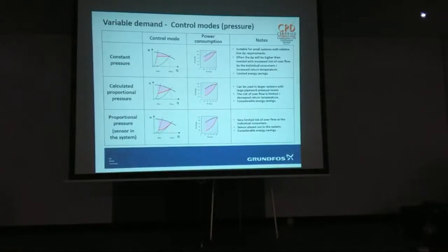Unless you just need to have a sensor in the other place, across the manifold. If you move this sensor away from the furthest point, you get a rising pressure at the end of the circuit. You still get the decreasing pressure at the pump, so you save energy, and maintain constant pressure at the point measured. So in the 2/3 of the way method, the pressure distribution diagram stays constant in the 2/3 of the way along. It rises at the end, so you get some potential imbalance after the sensor, and reduction in pressure before. Whereas if it's at the end unit, you get a reduction in pressure throughout the system.